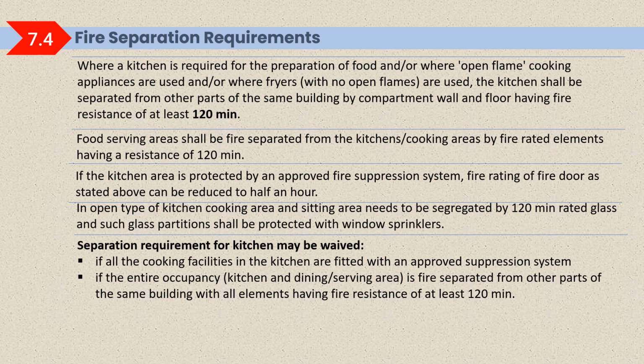Separation requirement for the kitchen may be waived off if all cooking facilities in the kitchen are fitted with an approved fire suppression system, and if the entire occupancy, kitchen and dining service area, is fire separated from other parts of the same building with all elements having fire resistance of at least 120 minutes. So this is one of the new things that has been added. If other parts of the building are compartmented by 120-minute fire resistance, and the cooking facility is protected by the approved fire suppression system, then you don't need to provide separation between the kitchen and dining area.